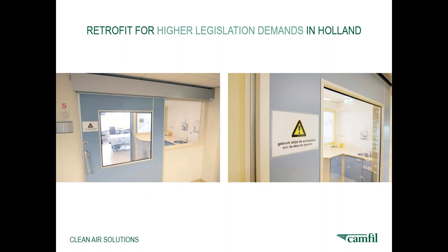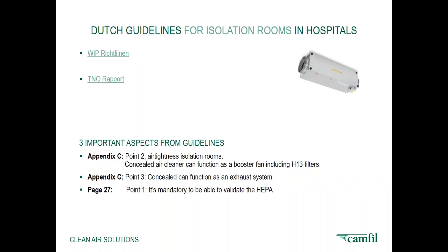Retrofit for higher legislation demands in Holland. The reason for doing this installation was the WIP guideline and the TNO report. Three important aspects for air cleaning to fit perfectly as a retrofit into these guidelines: in Appendix C.2, air tightness of isolation rooms, our Conceal can function as a booster fan, including H13 filters. Therefore, no other changes have to be made.